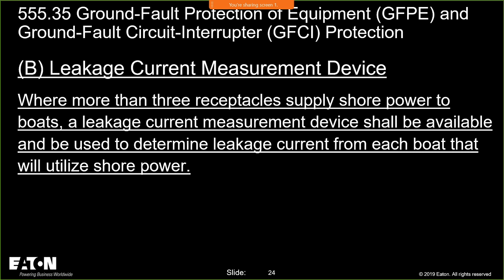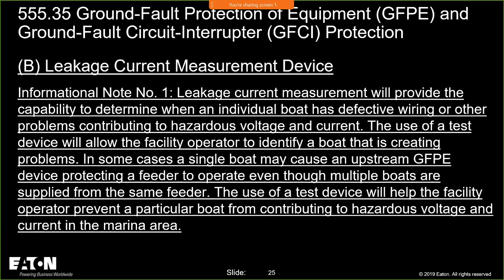What they did was say where more than three receptacles supply shore power to boats, you need to have this leakage current measurement device. This is because the complaint was: I have all these boats in place, and one bad actor comes in, plugs in, and takes the whole marina down. So we're trying to instill an act to get these boats and marinas to have a station where you test that boat before they plug in. If they pass the test, you send them to your electrified bay. If they don't pass, you tell them to go to that unelectrified docking facility.